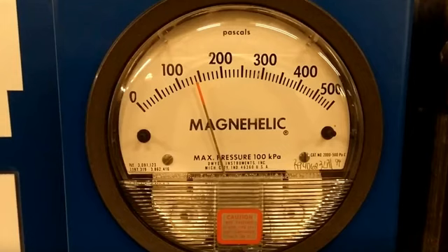Now, the filters do vary by energy efficiency, set by different standards. So the higher efficiency ones will create a lower pressure drop, and that means that your fans can overcome that pressure a lot easier. Well, there's just less pressure to overcome, and probably the fans driving this are going to be around 5 to 10 kilowatts, and they'll be running maybe 12 to 24 hours a day. So there's potentially a lot of energy you can save just from switching to a more energy efficient filter.